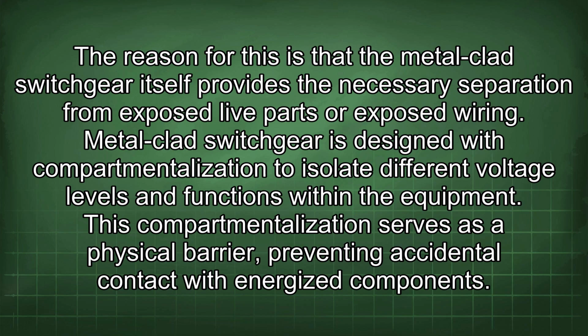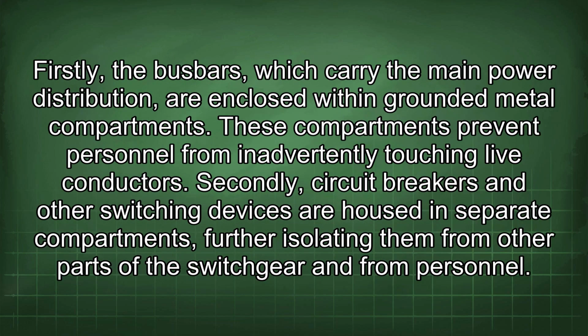The reason for this is that the metal-clad switchgear itself provides the necessary separation from exposed live parts or exposed wiring. Metal-clad switchgear is designed with compartmentalization to isolate different voltage levels and functions within the equipment. This compartmentalization serves as a physical barrier, preventing accidental contact with energized components. Firstly, the busbars, which carry the main power distribution, are enclosed within grounded metal compartments. These compartments prevent personnel from inadvertently touching live conductors.